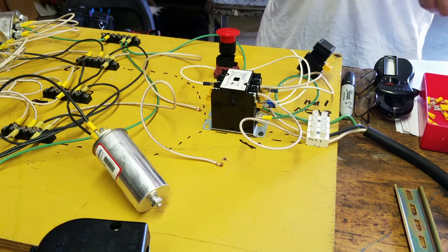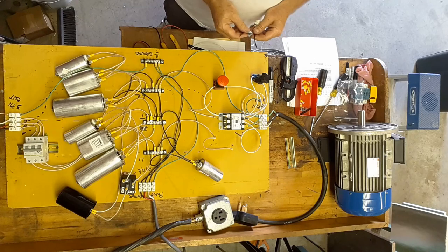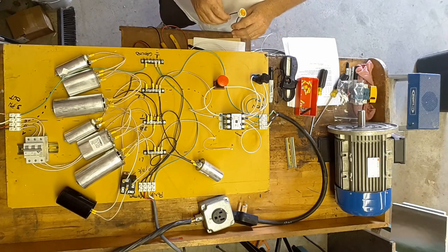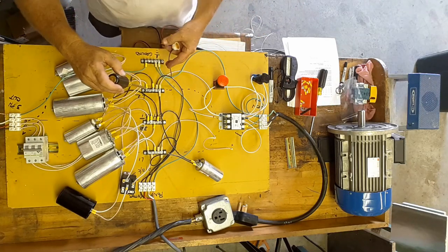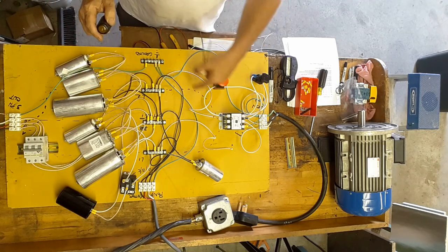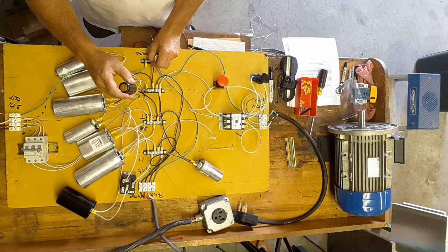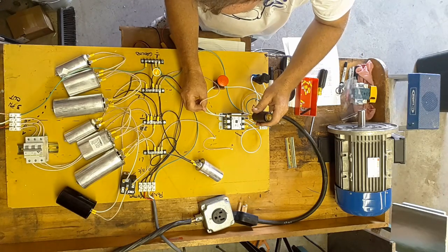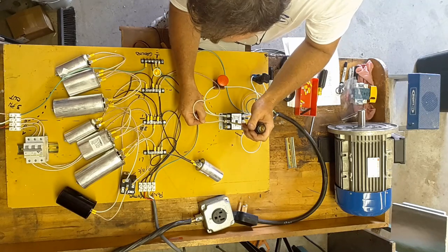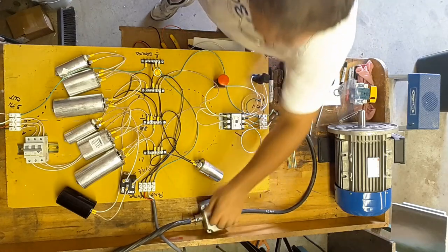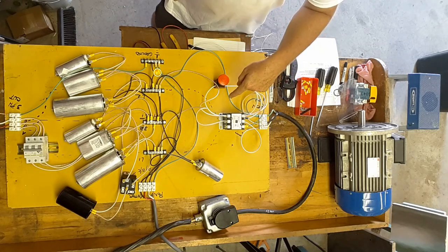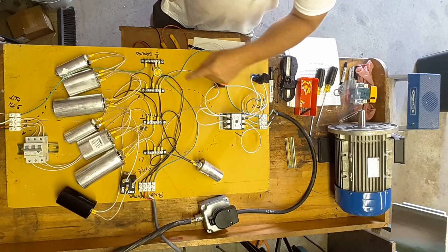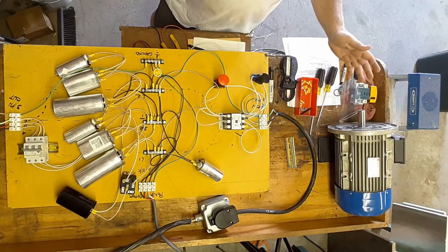One more thing. We need a light. We want to wire the light to be an indicator that we have power. I would say one of the best ways to do this is down here, off of one leg. This is a 110-volt indicator light. So in our panel, we could either run off of this side of the relay, which is the same as running off of one of these screws. So for now, let's hook our power back up, going out to the rest of the machine. One full system test. I push the button. The magnetic relay starts. The coil continues to work through this loop. The light goes on, indicating things are working. The motor starts and sits and runs.